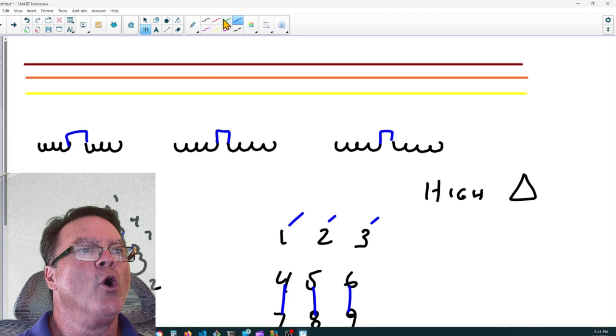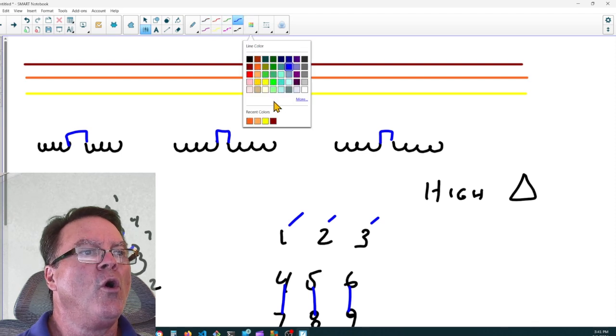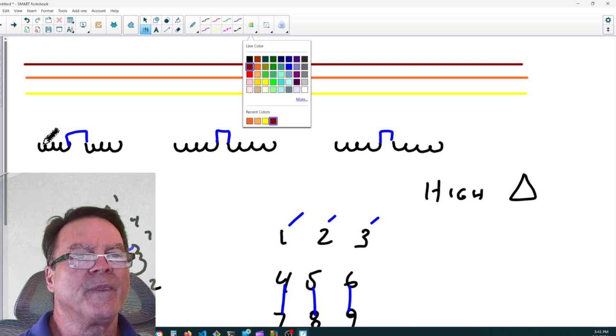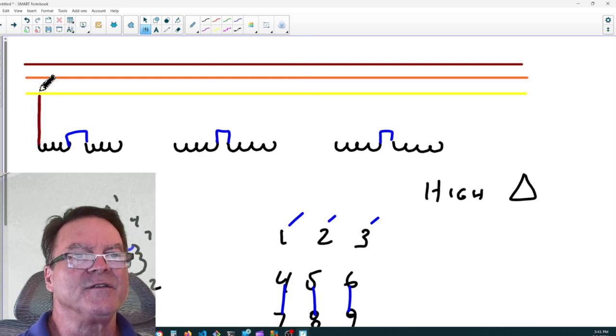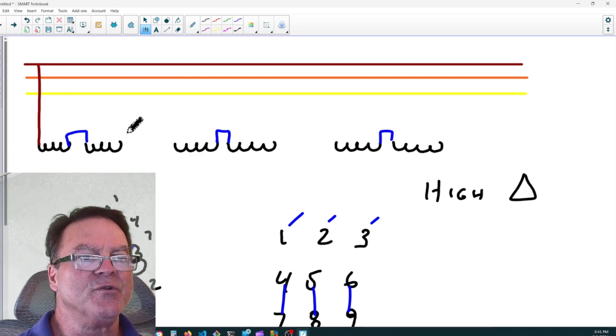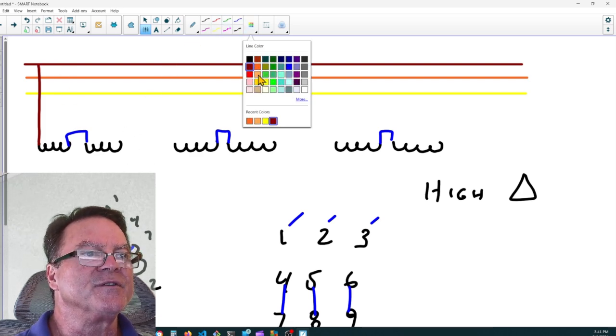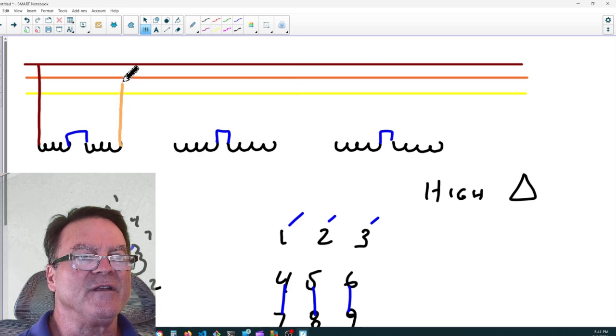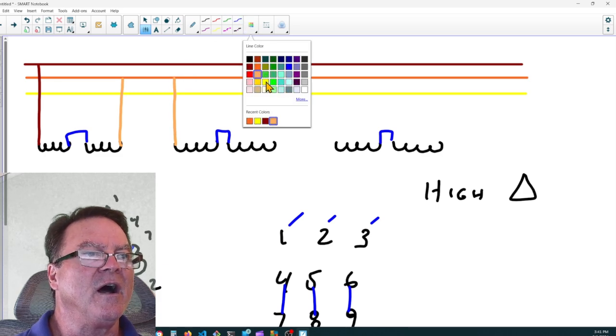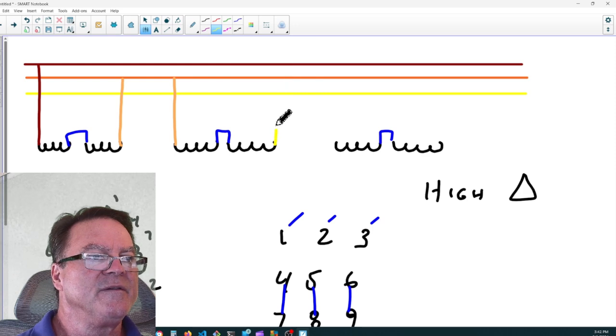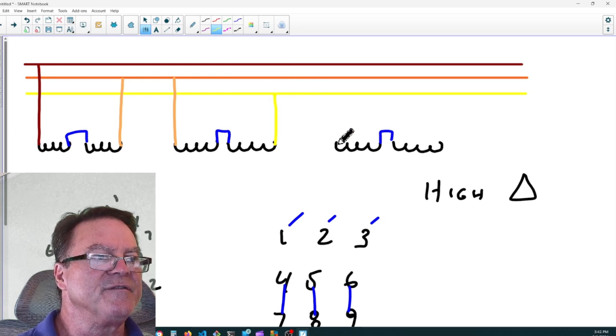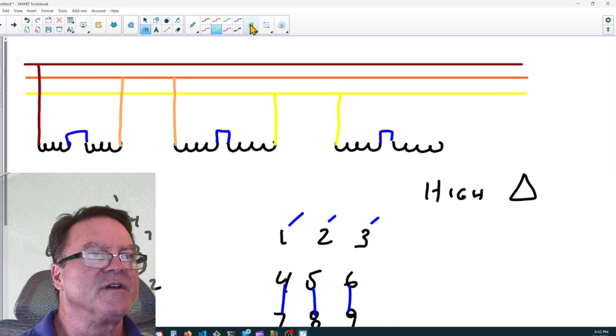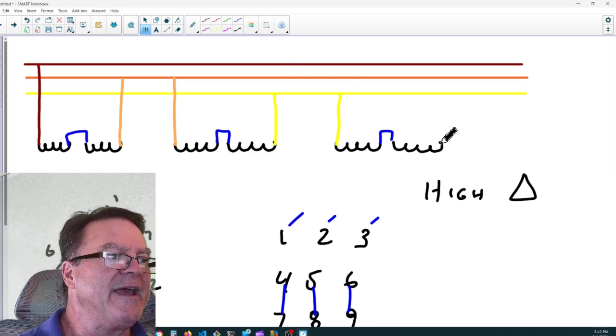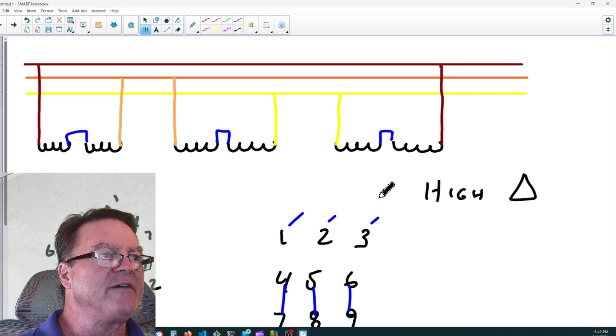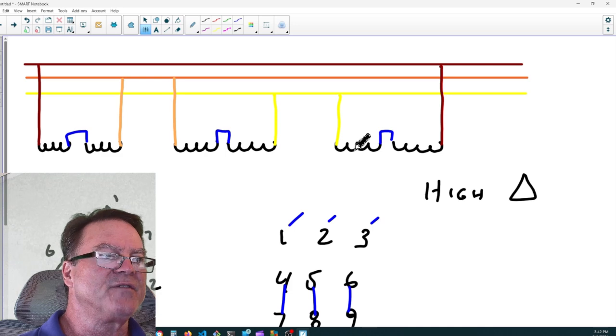And one goes to A phase. And remember, 10 and 2 are tied together. So I'm going to take 10 to B phase and 2 to B phase. And I'm going to take, on this second one, 11 goes to C phase, and 3 goes to C phase, and 12 goes to A phase. So that's high voltage for delta. We're going series for high voltage.